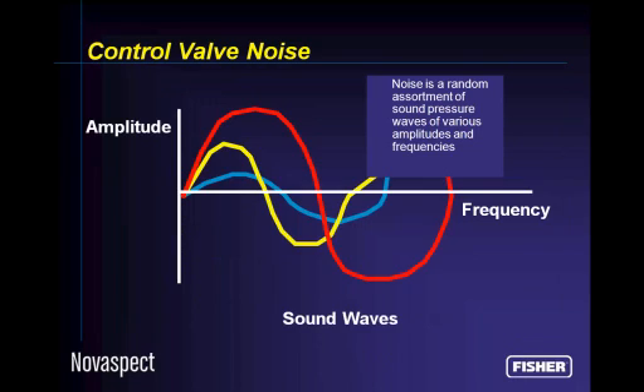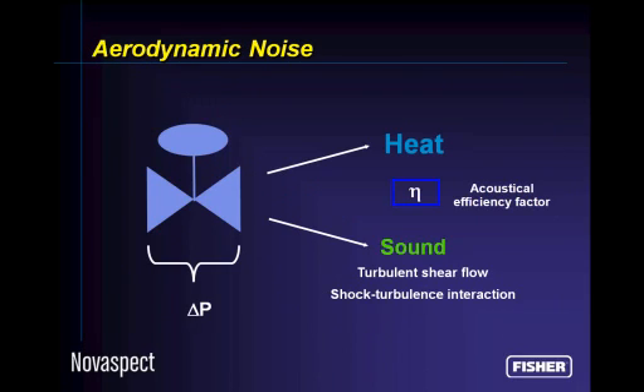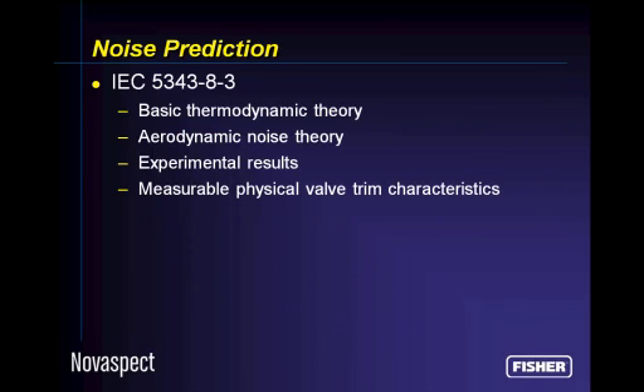You would think it's very difficult to calculate the noise level coming from a control valve, but it's not. We have an acoustical efficiency factor that we use to convert the differential pressure energy to two forms, heat and sound, and we can actually predict how much of that will become sound. We have an international standard that we all use to calculate the sound pressure level that's created by the control valve.